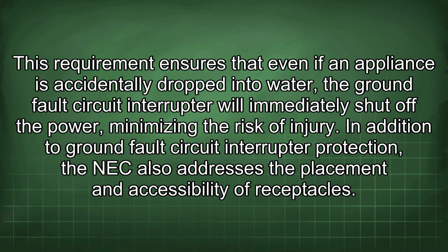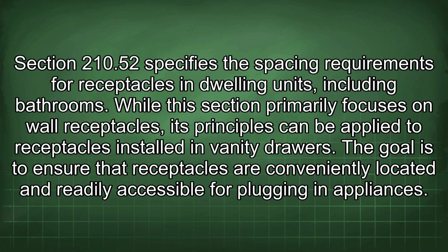In addition to ground fault circuit interrupter protection, the NEC also addresses the placement and accessibility of receptacles. Section 210.52 specifies the spacing requirements for receptacles in dwelling units, including bathrooms. While this section primarily focuses on wall receptacles, its principles can be applied to receptacles installed in vanity drawers. The goal is to ensure that receptacles are conveniently located and readily accessible for plugging in appliances.